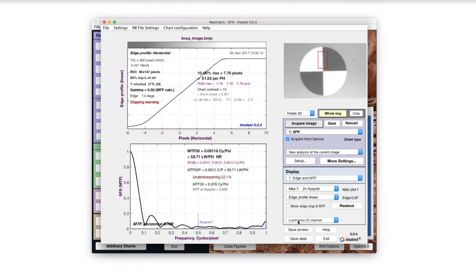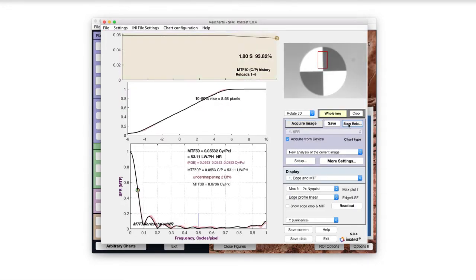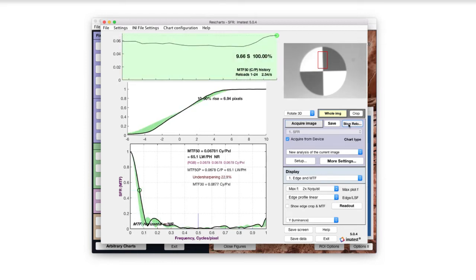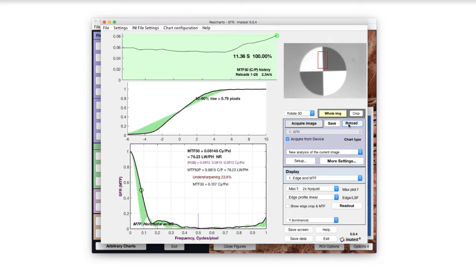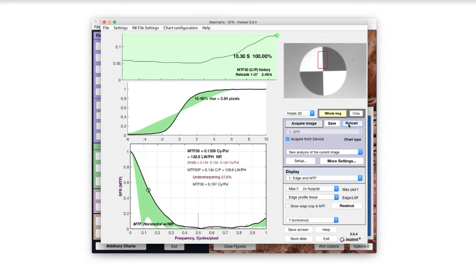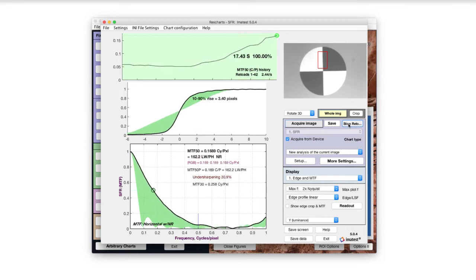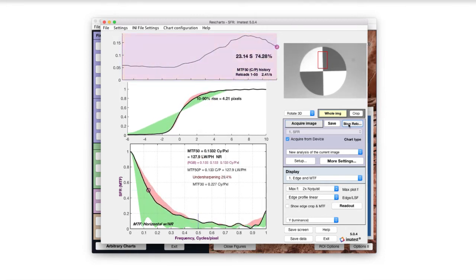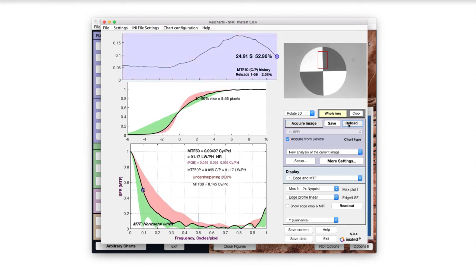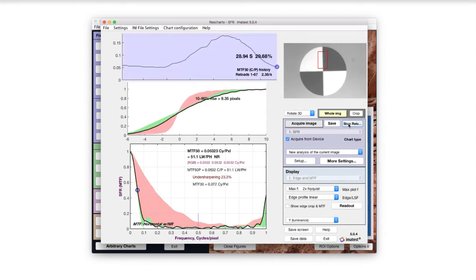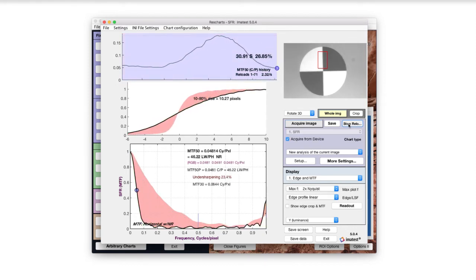As the image is brought into focus, the MTF of the image increases, indicated by the green area. Optimal focus is reached as the MTF measurement reaches a maximum. Focusing beyond this point results in a decrease of MTF, indicated by the red area.